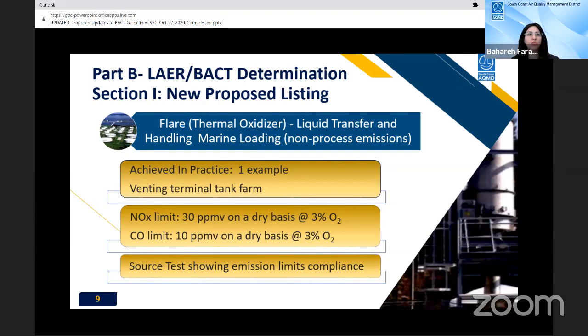We are on slide number 9, flare or thermal oxidizer. This control equipment is used to control vapors from marine loading operations in a terminal. In permit descriptions, it is sometimes referred to as a thermal oxidizer and sometimes as a flare, so we use them interchangeably. This facility has 2 parallel flare burners with a maximum heat release rating of 39 million BTU per hour each, and they can operate together or individually. They use natural gas to bring it up to temperature, and then natural gas goes to the burner and is injected into the vapor line at the duct.